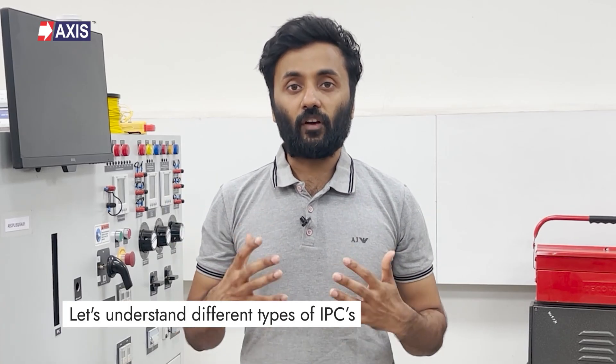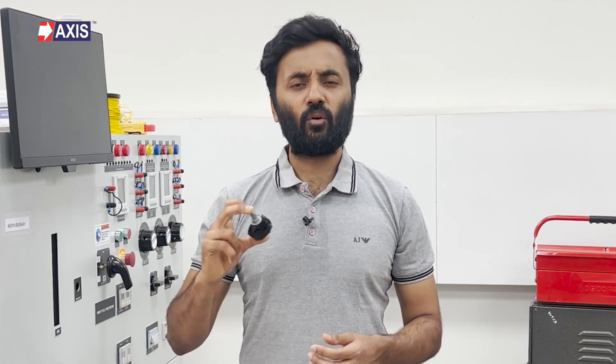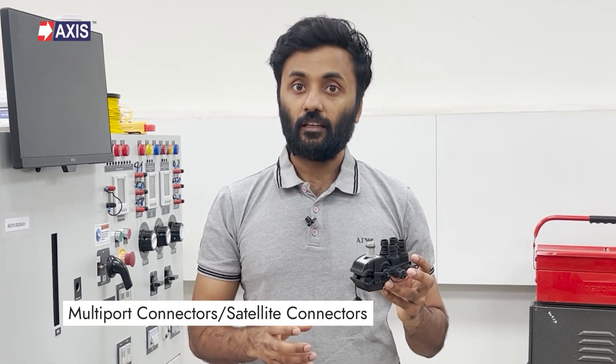Let's understand the different types of IPCs, focusing on the major ones used in AB cable systems. First, IPCs used in street light connections — these are generally used to tap the main AB cable and connect it to a service line that powers street lights or other applications. Second, the multi-tap connection type, also known as multiport or satellite connectors — these IPCs tap the main AB cable and bring power to households. It is called multiport because one tap connection from the main line can bring connections to multiple households.